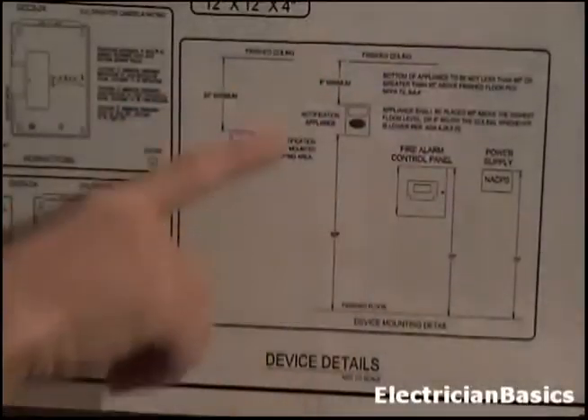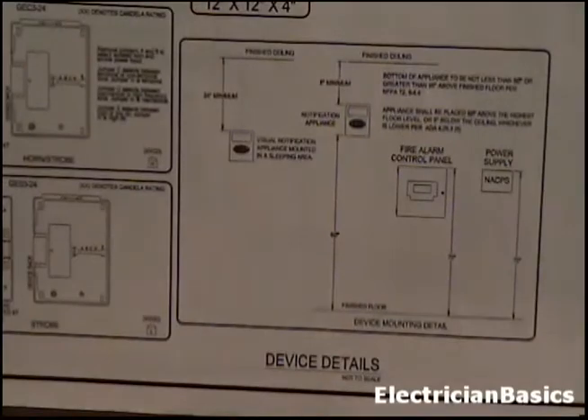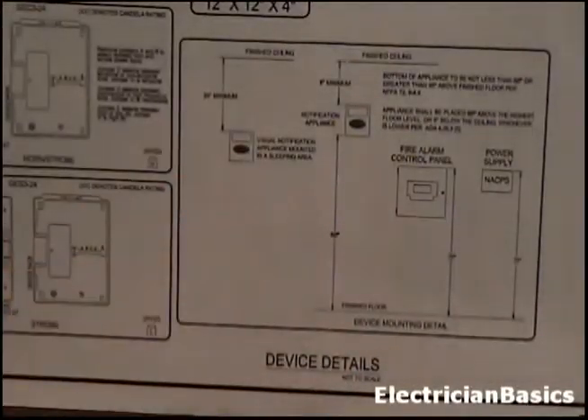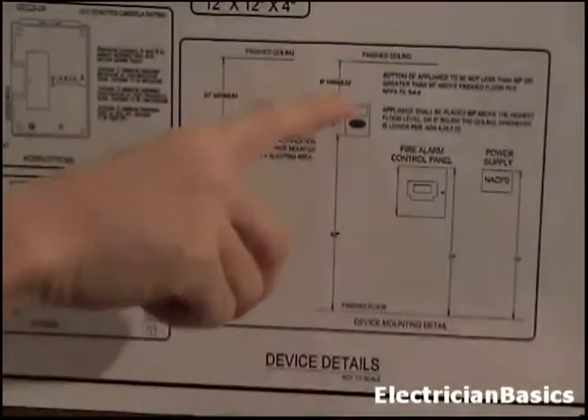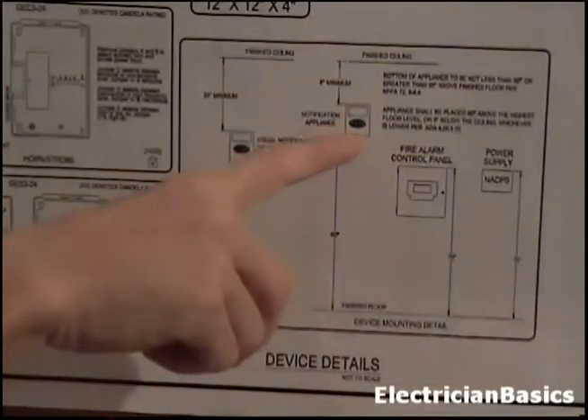Okay, we're looking now at the device details right here. It says not to scale, so I want to point that out, so you can't scale off in there. And it talks here, okay, a finished ceiling, 6-inch minimum from the ceiling to the top of the notification appliance.